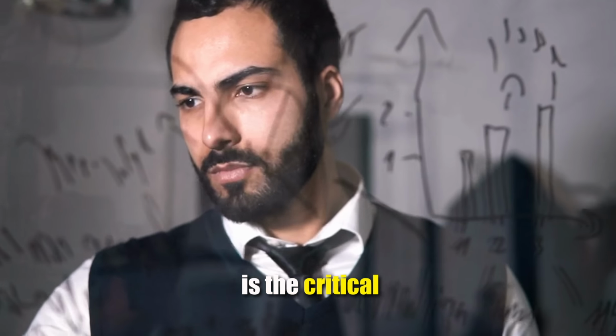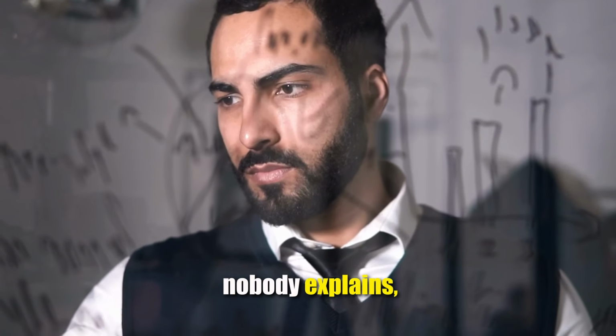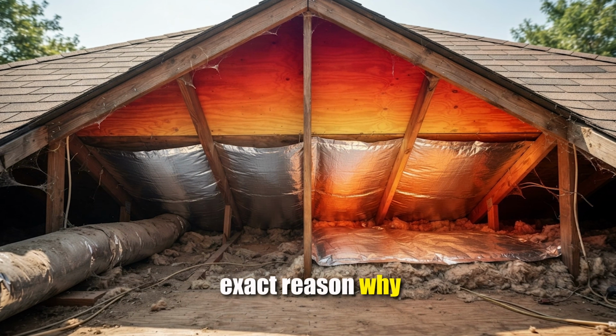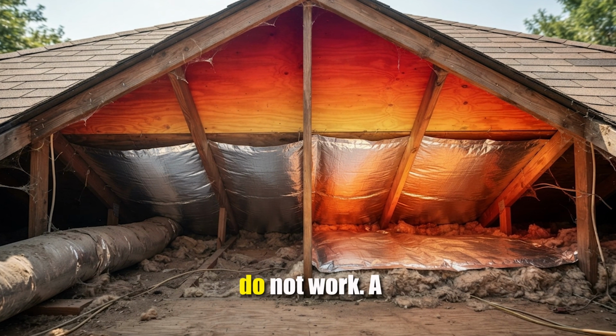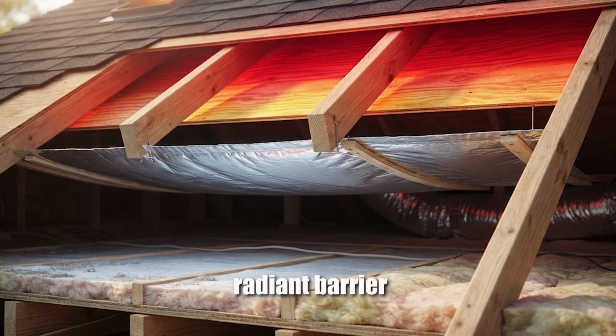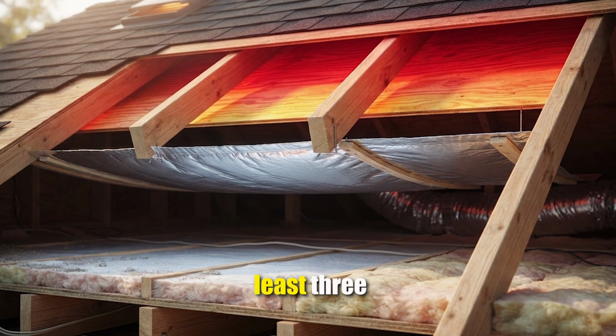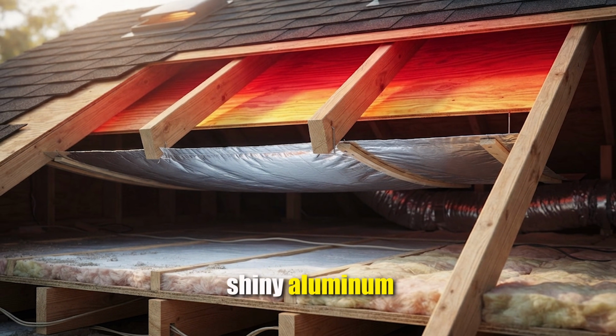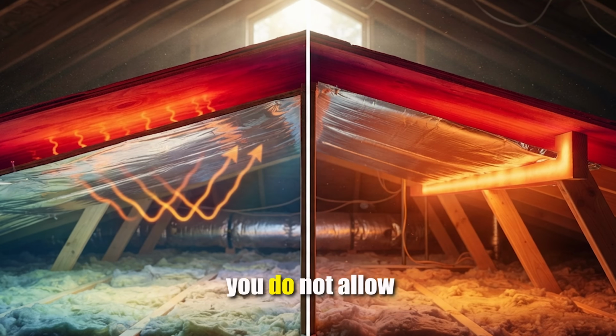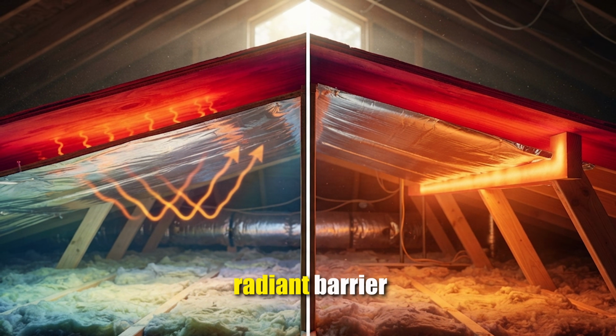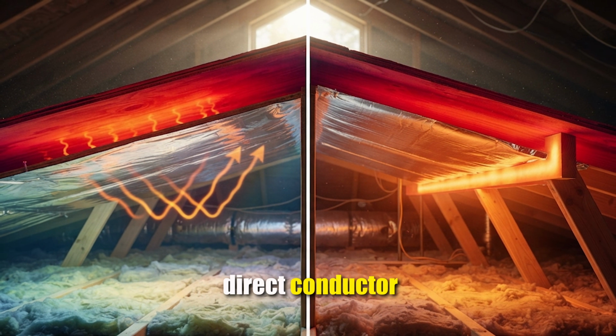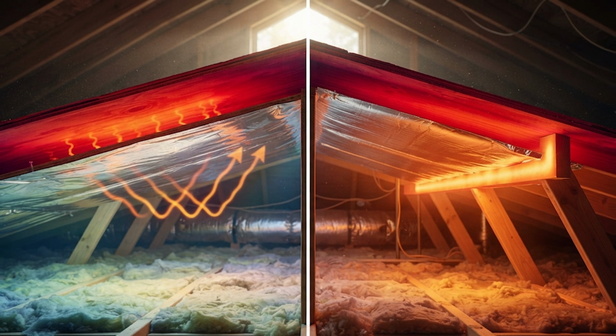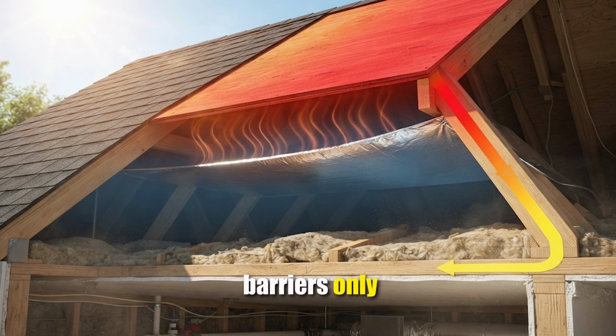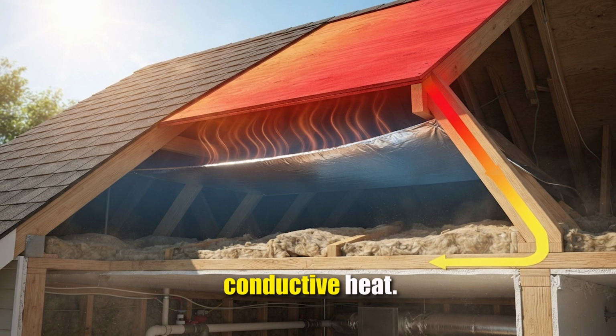Now, here is the critical placement rule that almost nobody explains, and it is the exact reason why some people claim that radiant barriers do not work. A radiant barrier must have an open airspace of at least 3/4 of an inch next to the shiny aluminum side to work. If you do not allow for this airspace, the radiant barrier will act as a direct conductor and pass the heat straight through. Remember, radiant barriers only block radiant heat, not conductive heat.